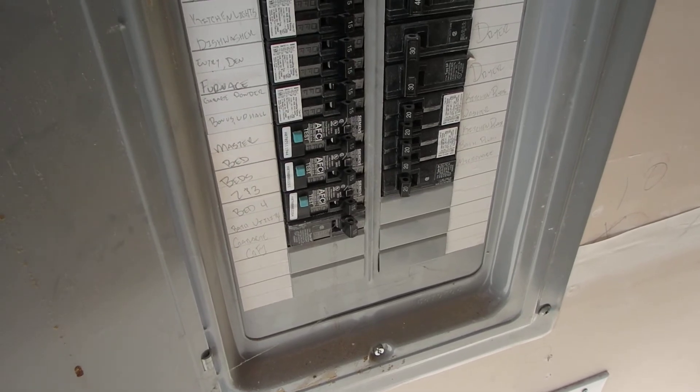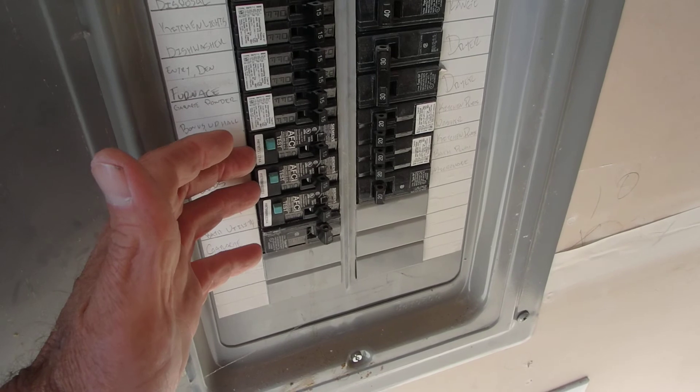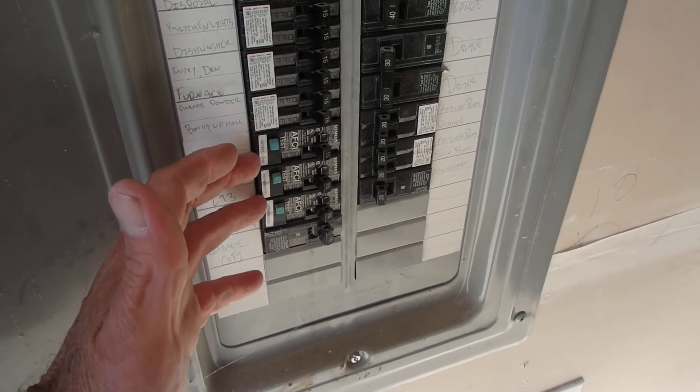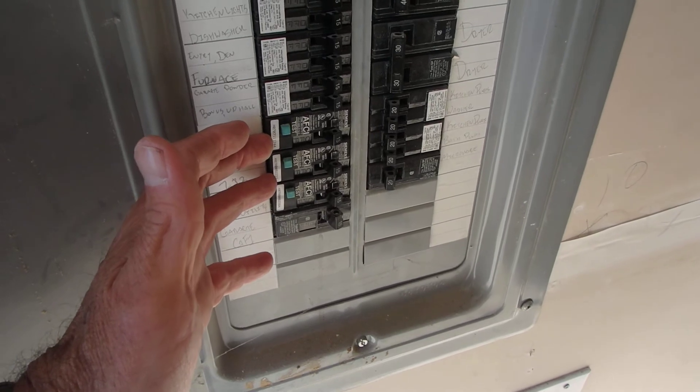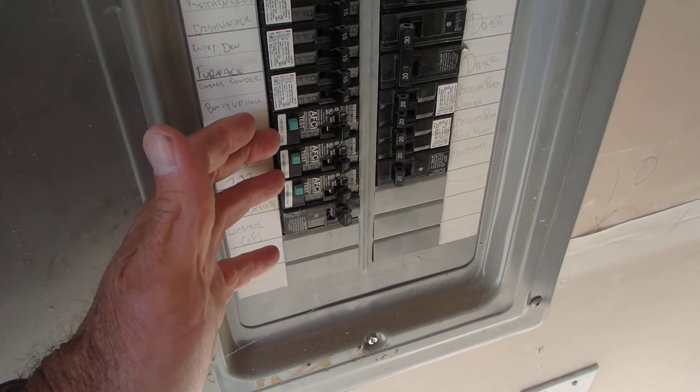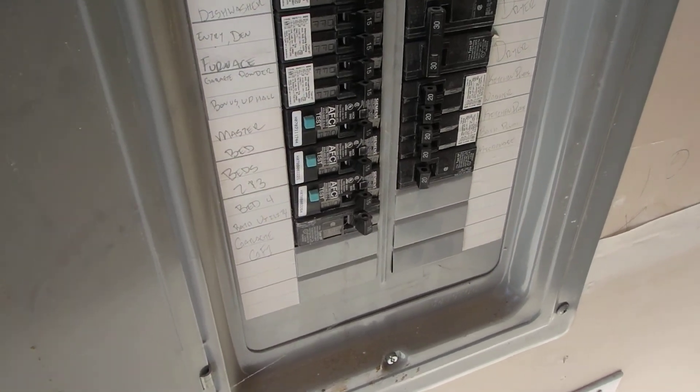But if you have a client, or you yourself have issues with nuisance tripping in a newer home, and obviously after the 2002 period when we started installing these, then you might want to think about changing out that arc fault to one of the newer ones. They perform quite well, and it's pretty rare to hear about a person having an issue with them.